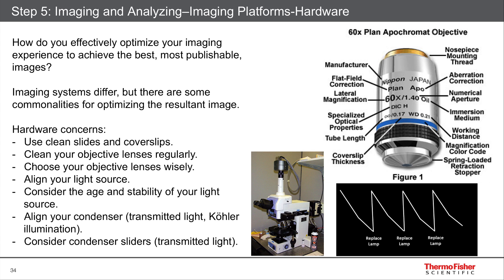Now let's talk about the instruments and the software. Here you can see an image of a typical objective lens used in a microscope. There are a lot of different aspects in choosing an objective, but generally you want to go with the best possible one. Usually an apochromatic, S-apo, or super-apochromatic is your best choice because it corrects for chromatic aberrations and planar aberrations, giving you a nice, uniform image that co-localizes between colors easily. Consider the magnification you need — using oil will give you a brighter, more resolved image, but oil has its own issues.